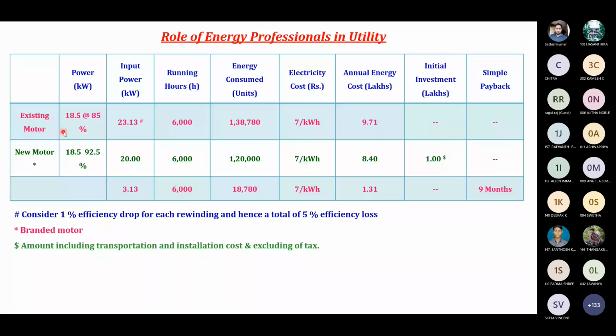So the existing motor is 18.5 kilowatt at an efficiency of 85%. Now this is the output power, not the input power. Whatever is available in the nameplate is the output power. Let us consider that every rewinding causes 1% efficiency loss. Normally 2 to 3% efficiency loss will occur, but assuming 1% efficiency loss, 80% is the new efficiency. So 18.5 kilowatt divided by 0.8 is the input power. Output power divided by efficiency equals input. So input power is going to be 23.13.